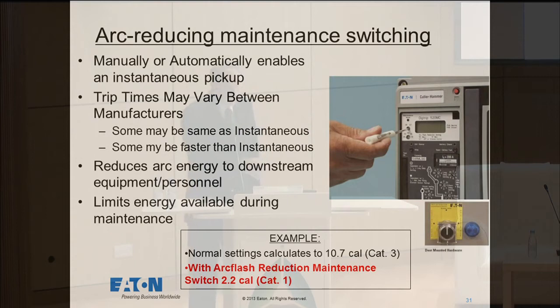Now, what this allows you to do is allow a maintenance worker to go in and say, I'm going to do some sort of maintenance in this equipment, but I want a lower amount of energy. While I'm there, I hit this one button. It's a maintenance switch. It automatically overrides all the other settings so that if anything should occur while this person's in there, the time and all the settings go all the way down to their minimum. In fact, this is faster than what the ordinary minimum is because it bypasses all the logic.